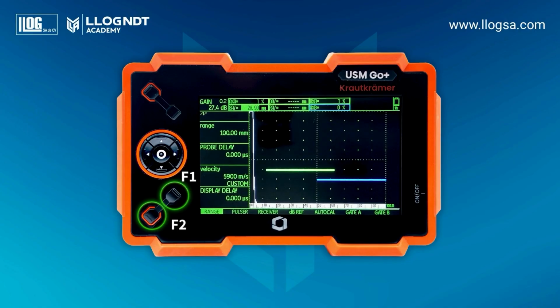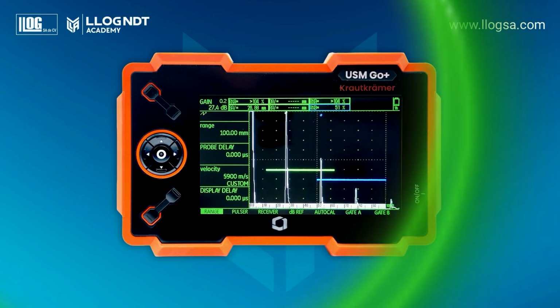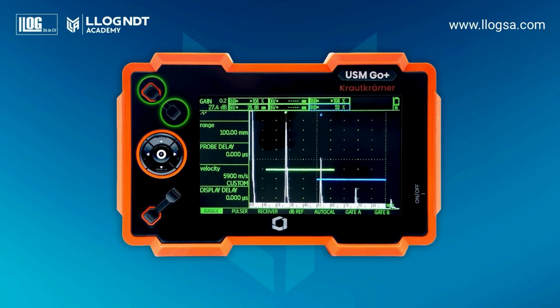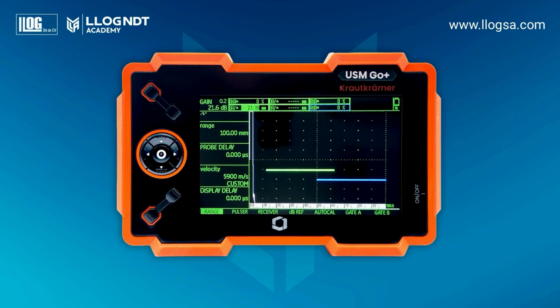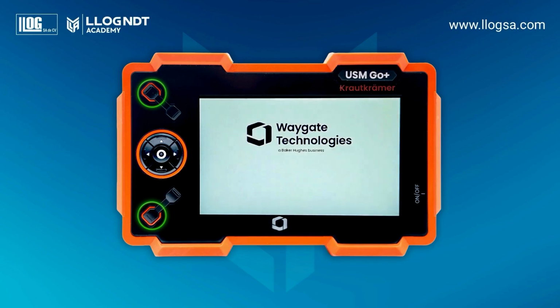Some actions can also be performed using key combinations. If we press the top keys simultaneously, once, the gain will automatically adjust to bring the amplitude to 80% of the echo intercepted by the gate. To perform a system reset, press and hold the gain increase key and the function 2 key. Then power on the unit. At the bottom of the display, a message will appear, indicating that the unit has been successfully restored.